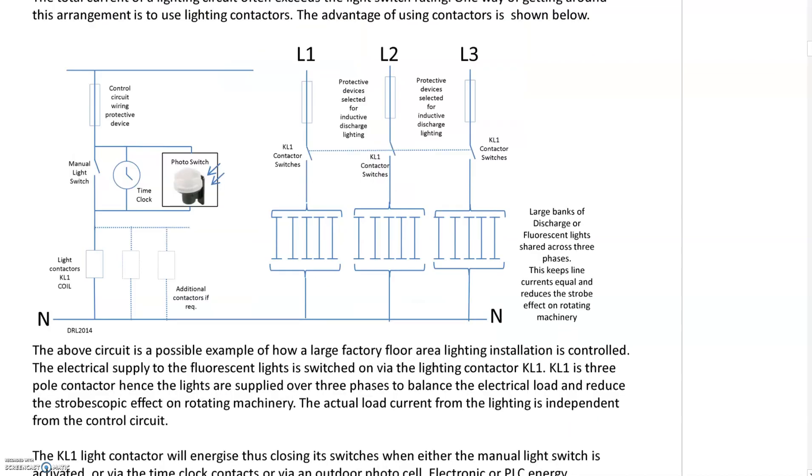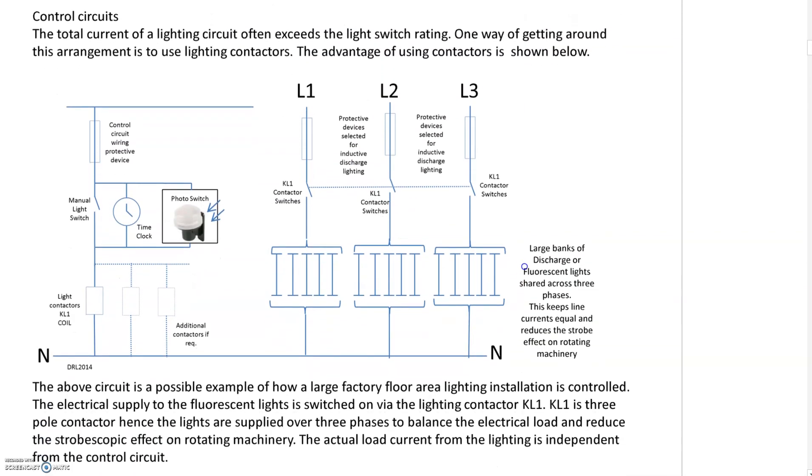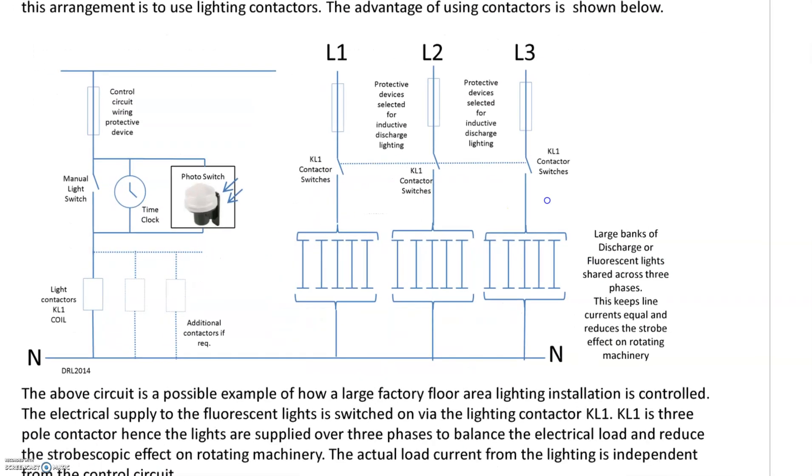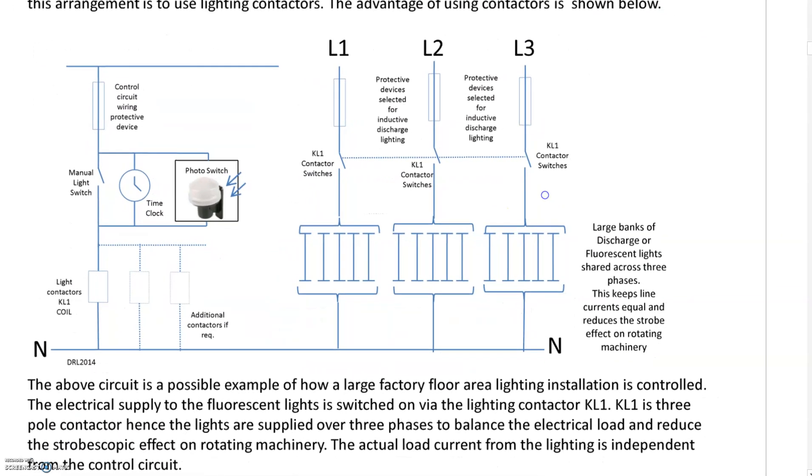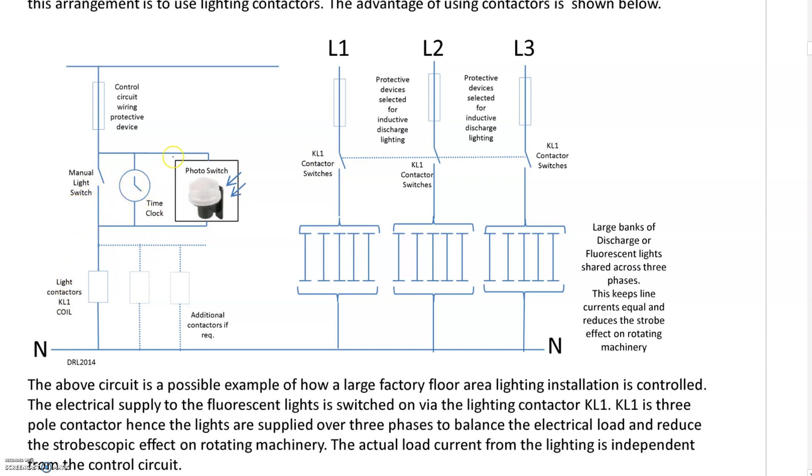One way of controlling lighting in an industrial or energy efficient way is using time clocks, dawn-dusk sensors or photo switches, and lighting contactors. You can have a manual switch, time clock, or photo switch. Manual switch overrides the time clock, time clock overrides manual switch. You could even put smart technology in there for remote control by phone or BMS building management system.